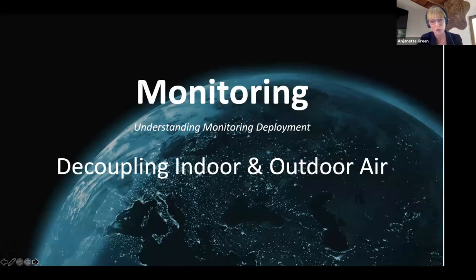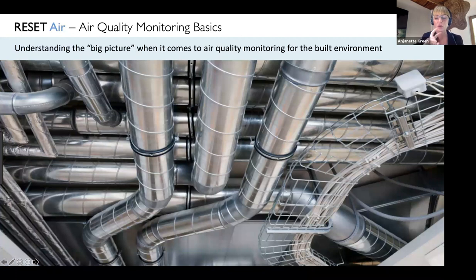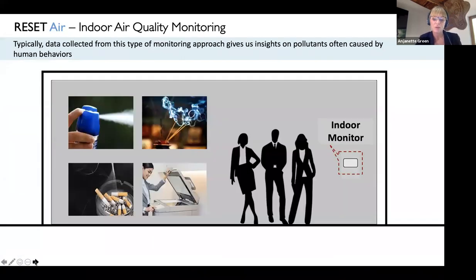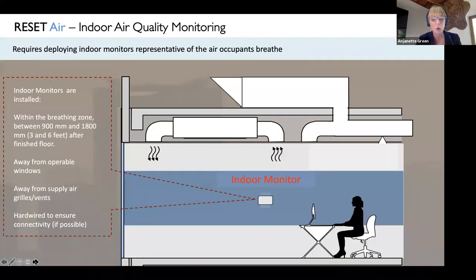Let's talk about monitoring and how we decouple indoor and outdoor air quality data. There are two approaches: first, indoor air monitoring, where monitors are placed in interior spaces and data gives insights on pollutants caused by human behaviors — like particulate matter from secondhand smoke or vacuuming, or VOCs released from cleaning products. Reset codifies how monitors should be installed — they must be placed within the breathing zone and away from operable windows and air supply sources.